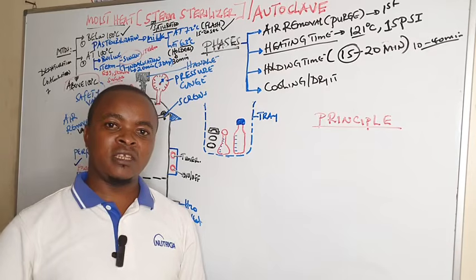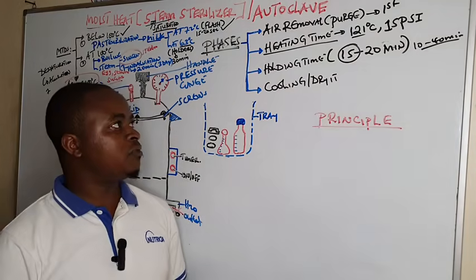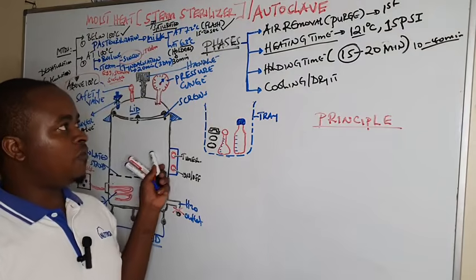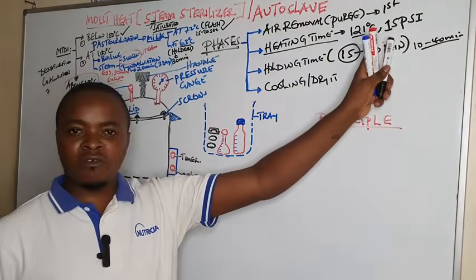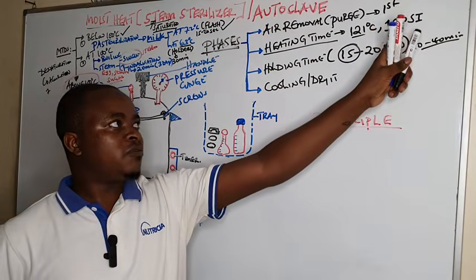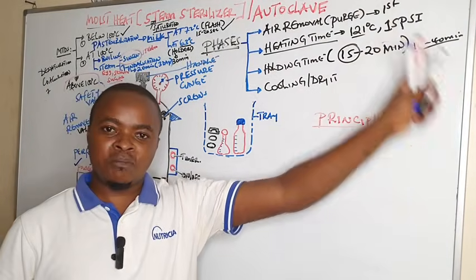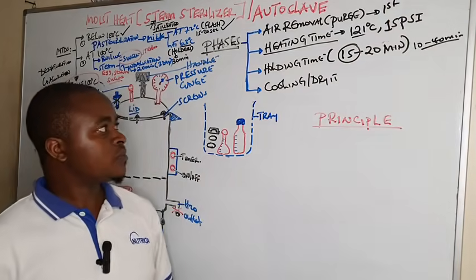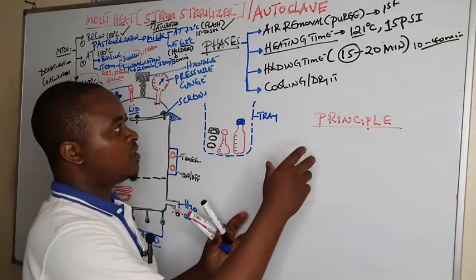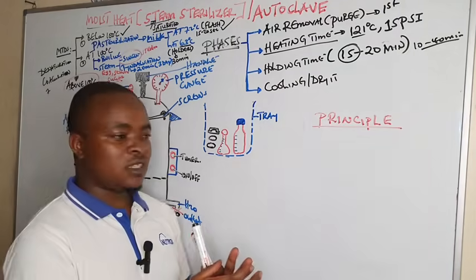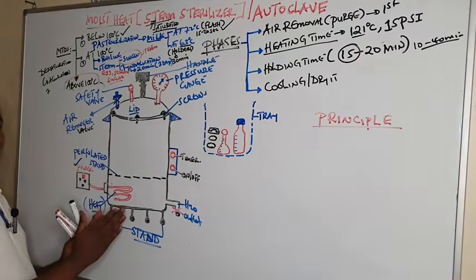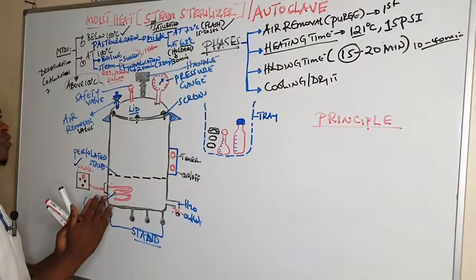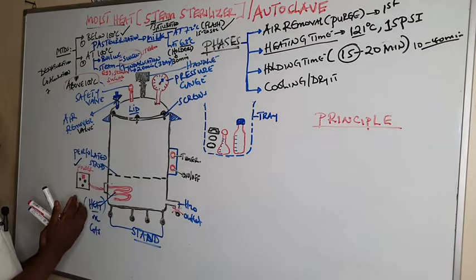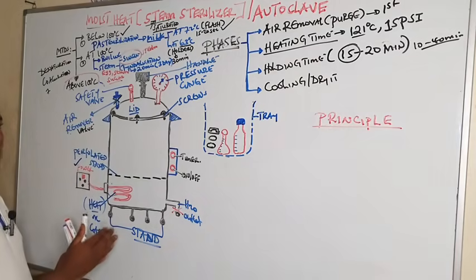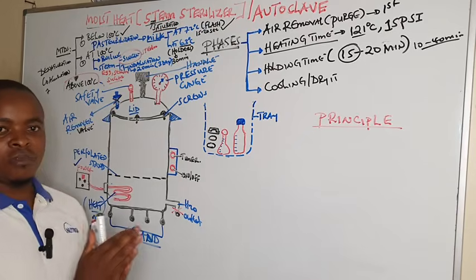The time taken to completely sterilize equipment in the autoclave is at a high temperature of 121 degrees centigrade at 15 pounds per square inch. Then the last phase, after sterilizing, we switch off the autoclave. After switching off the autoclave, we open the air remover and the safety valve, and we allow it to cool to the temperature below 100.